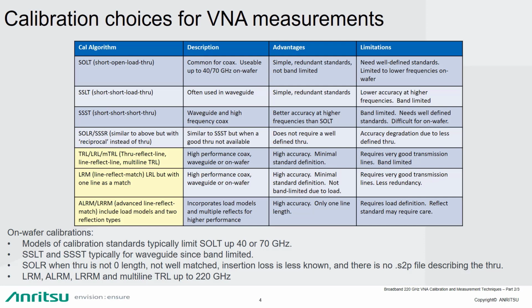LRM is similar to LRL, except instead of just using lines, you would use a match for one of your lines. And so the TRL and LRL are sometimes considered band limited because of the multiple lines that you might need to use in order to get down to the lower frequencies. And sometimes there's going to be a real estate issue on the substrate to have very long lines in order to get down to low frequencies. So the LRM is a good alternative to that in order to get to the lower frequencies.